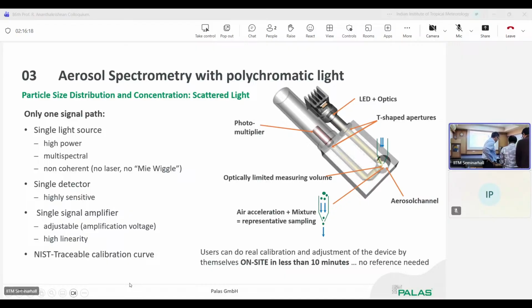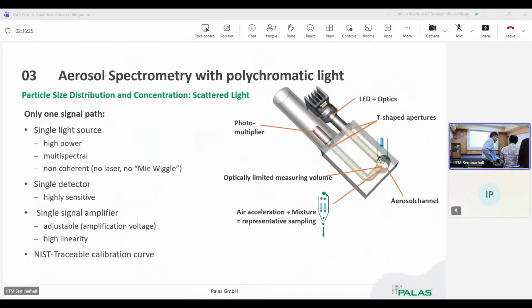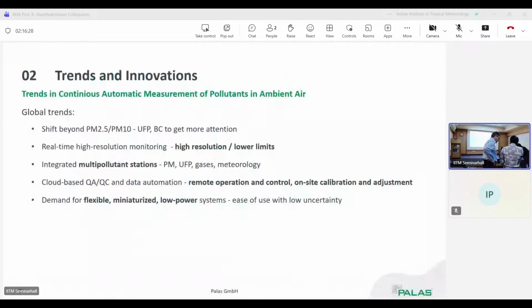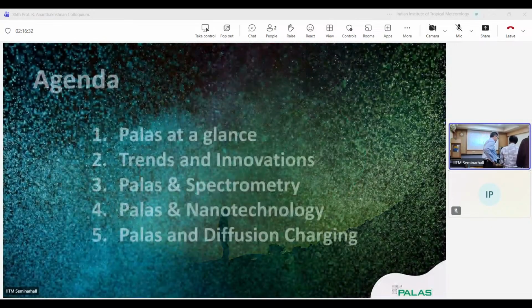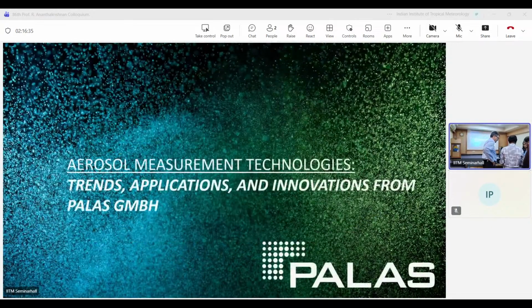The size range here for the system is too high. It's better to start at least at 0.2. This is the one for air. So these are two different sensors, one for medium concentrations. There are different options. One is the wide area number concentrations, and these are high concentration sensors up to 200,000 particles, and other sensors which may go up to 2 million.